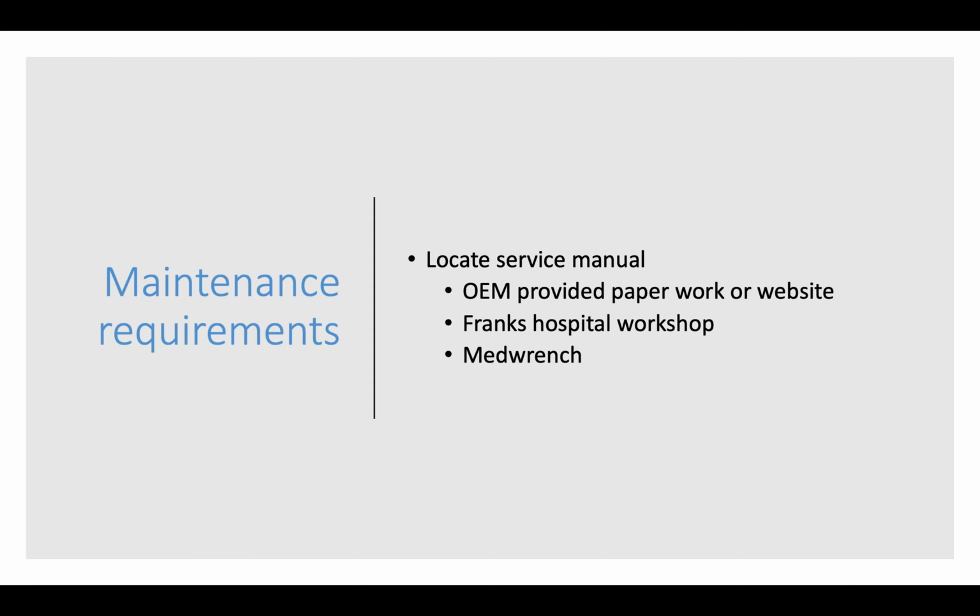Okay, so anytime you're doing maintenance, you want to make sure you locate the service manual. You can do that by using the OEM provided paperwork or website. A lot of times Frank's Hospital Workshop will have the service manual, or even MedWrench often has the service manual for different devices.